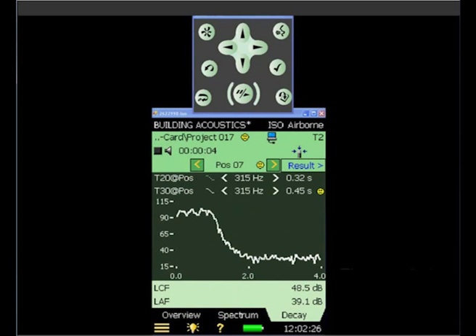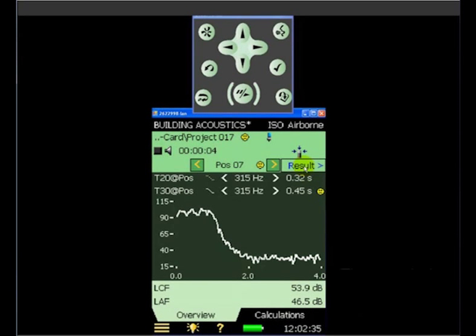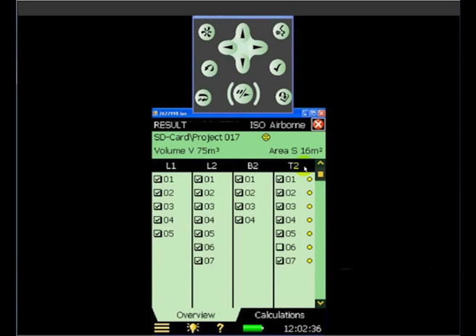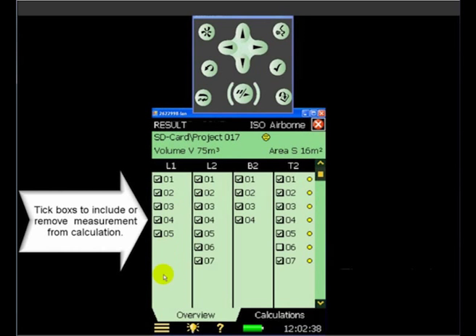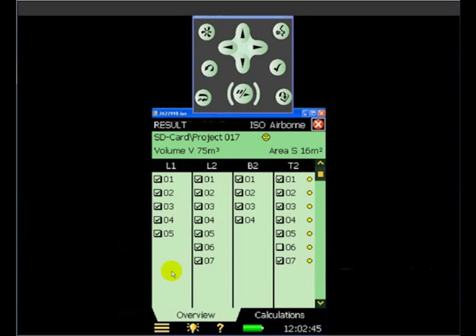So having completed our measurement, we're now ready to calculate our single figure index. So if we click on the result icon, or the result field, we can see that in summary we have a selection of measurements in each of the required locations. Source room, receiving room, background, and T2.